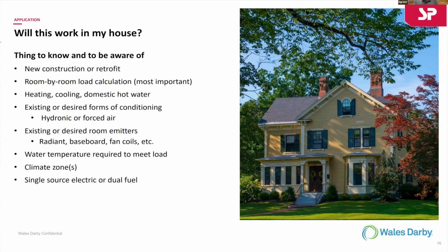We can use it in new construction where you're laying out the whole job, so you can mix and match the newer types of heat emitters in the house, or we can retrofit it to an older house or an older building. What becomes really important here is that, unlike the refrigerant systems where you're worried about the entire house's calculation, you still are worried about that in this sense, but you're not as concerned with oversizing for one season or the other, because we're heating and cooling water. What you're worried about is the emitters in each room. Are we putting enough baseboard to heat that room during the heating season? Because we're dealing with lower temperatures, we may have to run a little more baseboard than traditional.